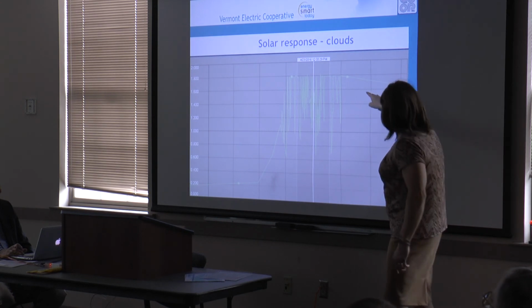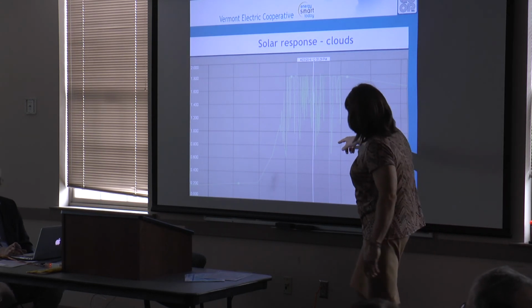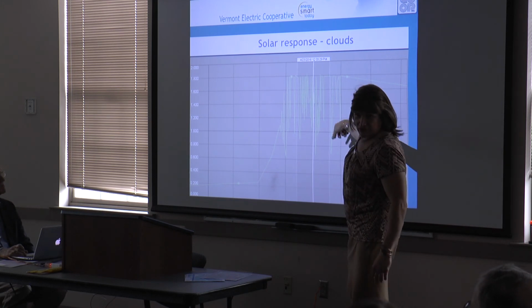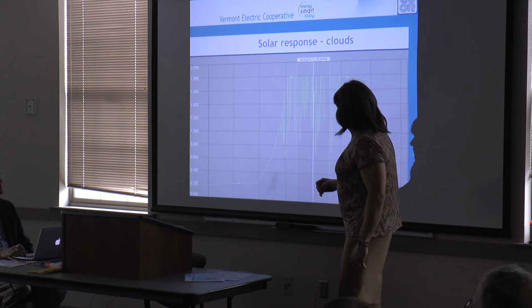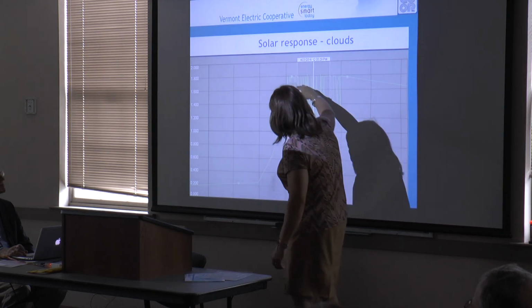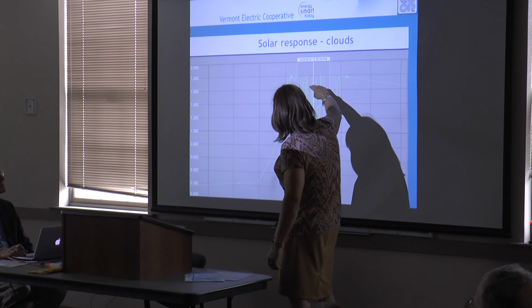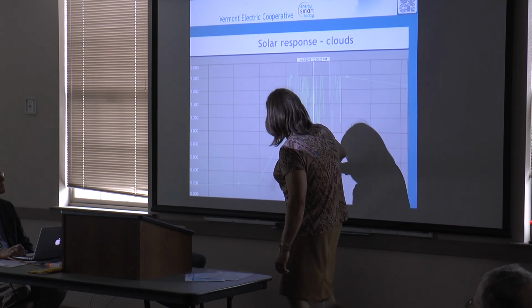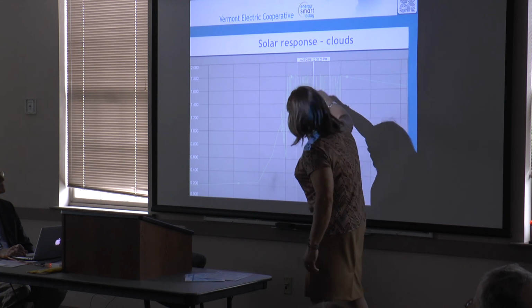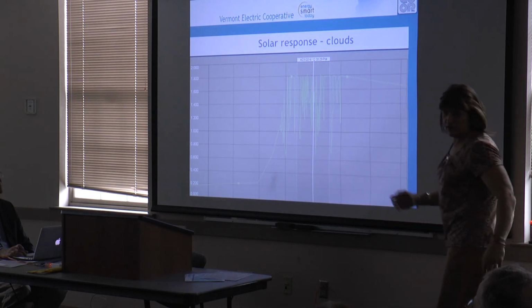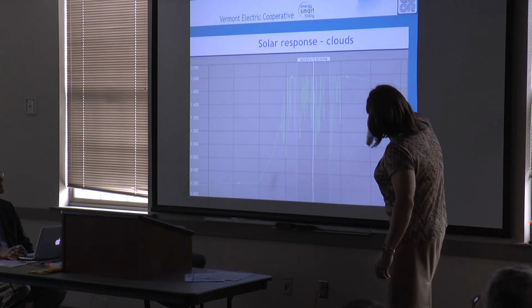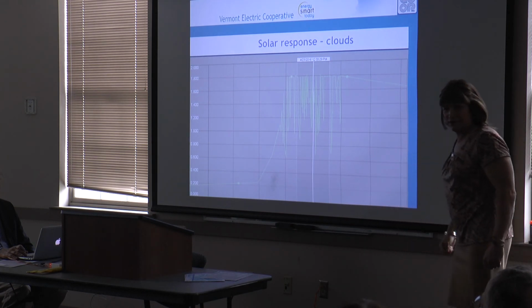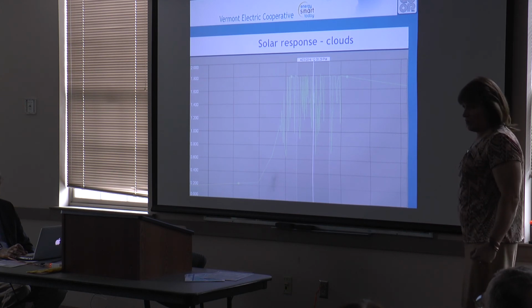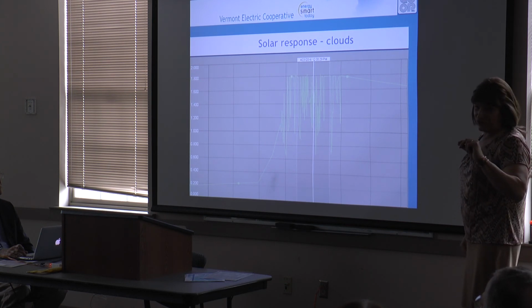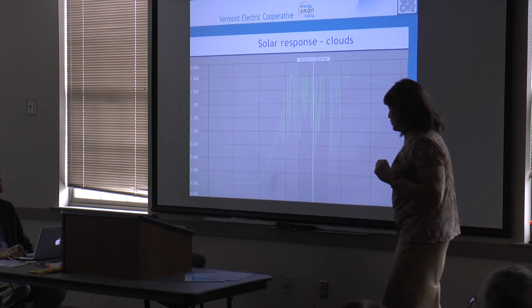With a spinning generator, output would stay flat and you'd adjust it when needed. This is what makes us crazy from an electrical standpoint. Trying to compensate for that is difficult. This system producing 1.8 megawatts, within about a 30-second period, goes down to 0.6. It loses 1.2 megawatts, more than half its output drops off. You can see on cloudy days they're cycling up and down. We're doing everything we can to protect your equipment from that. We watch our voltages, we've got our SCADA system. But remember, we're one of the most advanced utilities in the nation. Most utilities don't even have this capability to look at this.